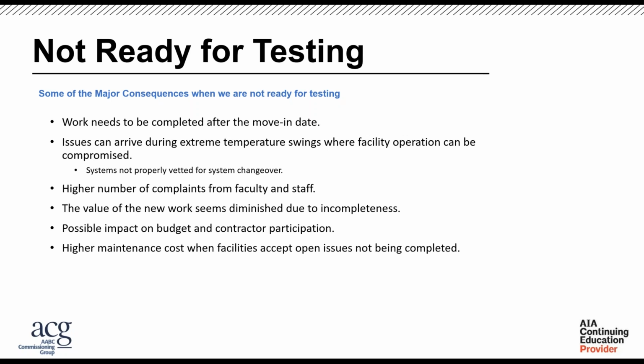Or there are opportunities where maybe there's a holiday or something. If you're trying to coordinate and work during school time, there's a school holiday or something that wasn't communicated, where their staff isn't available to let the team in. So it's just a lot of coordination that doesn't happen, and it all comes down to communication. Then you get more failed tests and retests, and it results in workarounds where we're not able to truly test the system once it's occupied, and we might have to look at pictures or trend data. Those are great as backups, but we should be able to fully test the system.